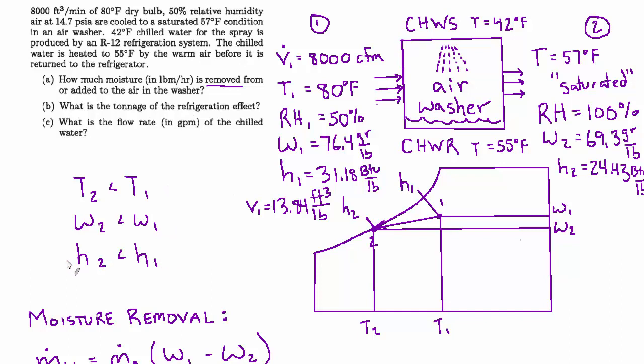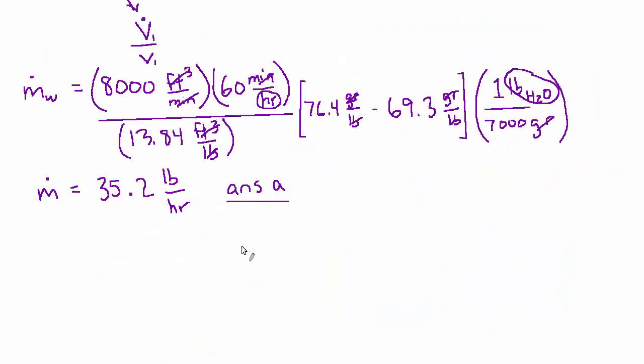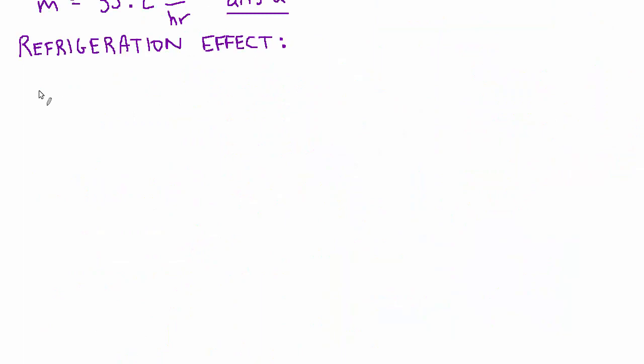The net cooling is captured by the change in enthalpy. So we're going to do a very similar calculation, but instead of using delta omega, we're going to use delta H. So let's set that up for the refrigeration effect. Now the formula we'll use will be Q dot, and this is Q dot total, because like we said, it includes sensible and latent. It's going to be based on delta H, which is the mass flow rate of air times h1 minus h2.